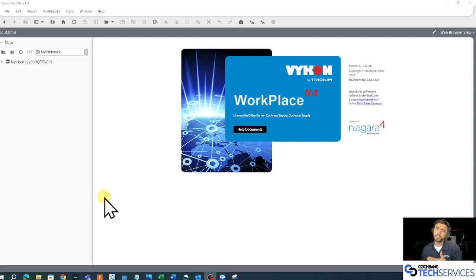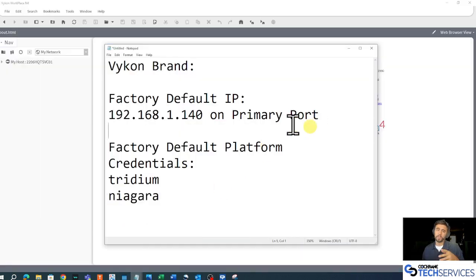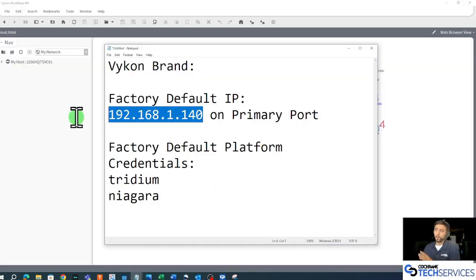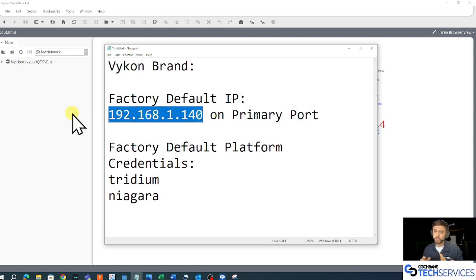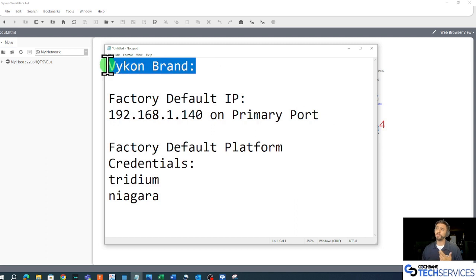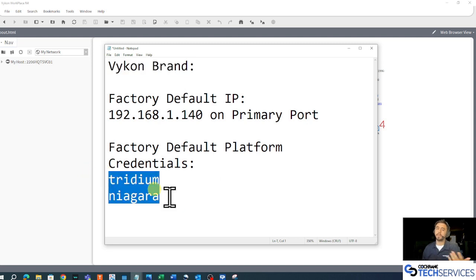We need to realize that a JACE has two different IP ports and we need to know which one we're using and what the IP address of that port might be. From the factory, our IP address on our primary port is 192.168.1.140. I'm using a Vykon-branded JACE, so the factory default platform credentials will be tridium niagara.